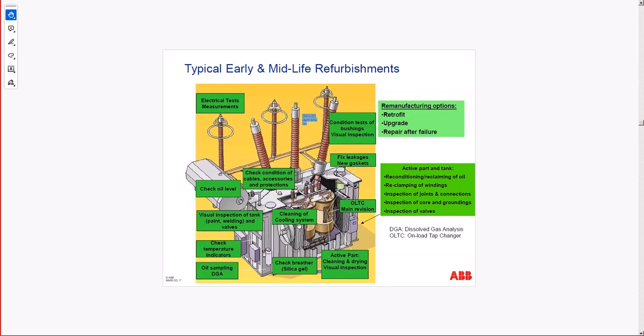As tap changer construction, we have the oil-cooled type and the vacuum type. The vacuum is the new one, and they last 1 million operations. The oil one is half, like 500,000 switching operations.